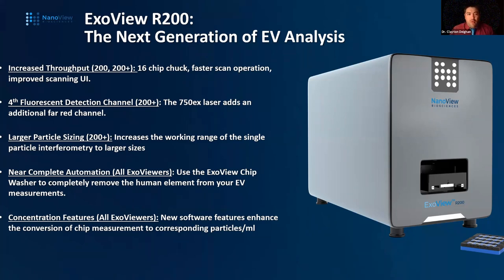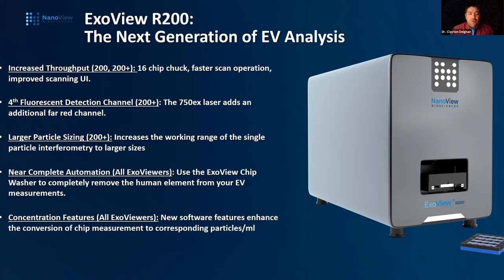The R200+ has some really cool features: mainly the fourth fluorescent detection channel. The R200+ comes with a fourth fluorescent color, which means you can do five-marker co-localization on single EVs. This laser is at 750nm excitation, adding a far-red detection channel beyond the standard red channel that excites at 647nm. Larger particle sizing is also in the R200+, using longer laser wavelengths to perform the same type of single-particle interferometry but at bigger sizes.